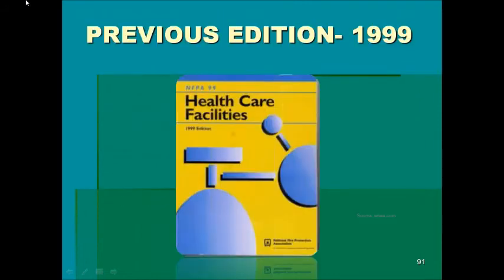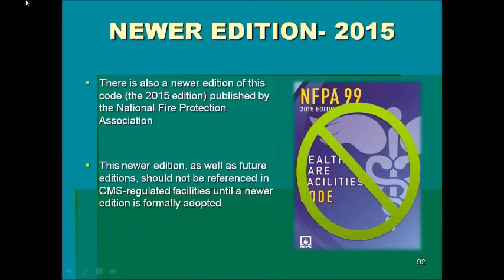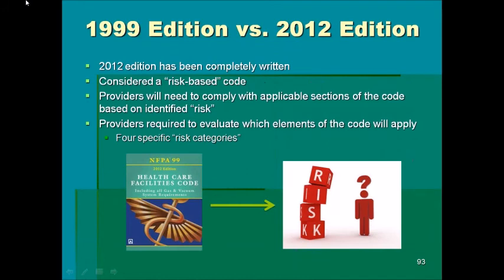The previous edition of NFPA 99 was the 99 edition, which was a standard. The new edition is a risk-based code. And even though there is a newer edition of NFPA 99 published, it is the 2012 edition of the code that you must comply with. You've got to understand that the 2012 edition versus the 99 edition of NFPA 99 is completely rewritten. It's a risk-based code, and it's applicable to you as a provider based on the levels of risk that you identify through a self-assessment process. The 99 edition and previous editions of NFPA 99, the Healthcare Facilities Code, was a healthcare standard that applied in total to every healthcare provider.